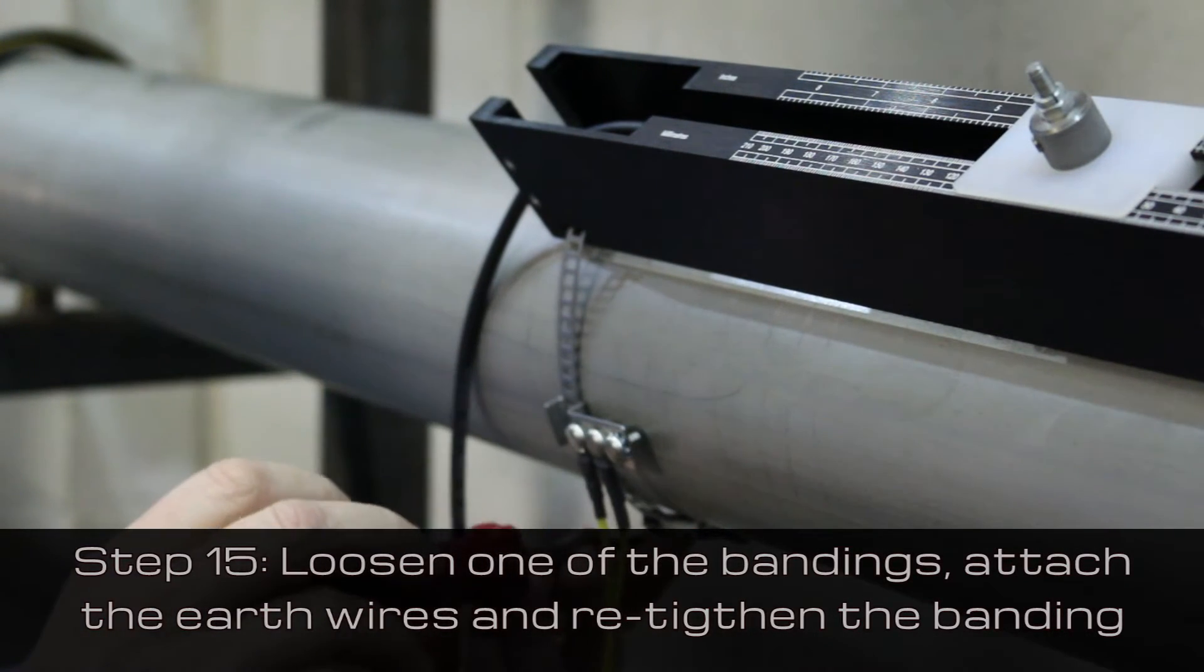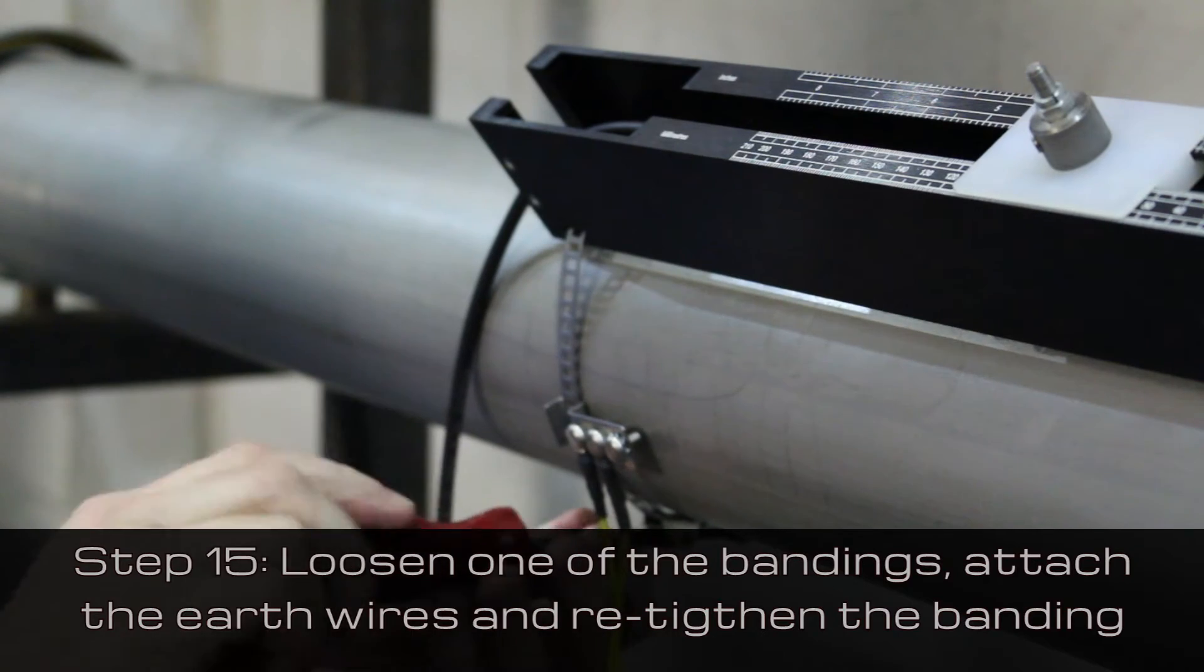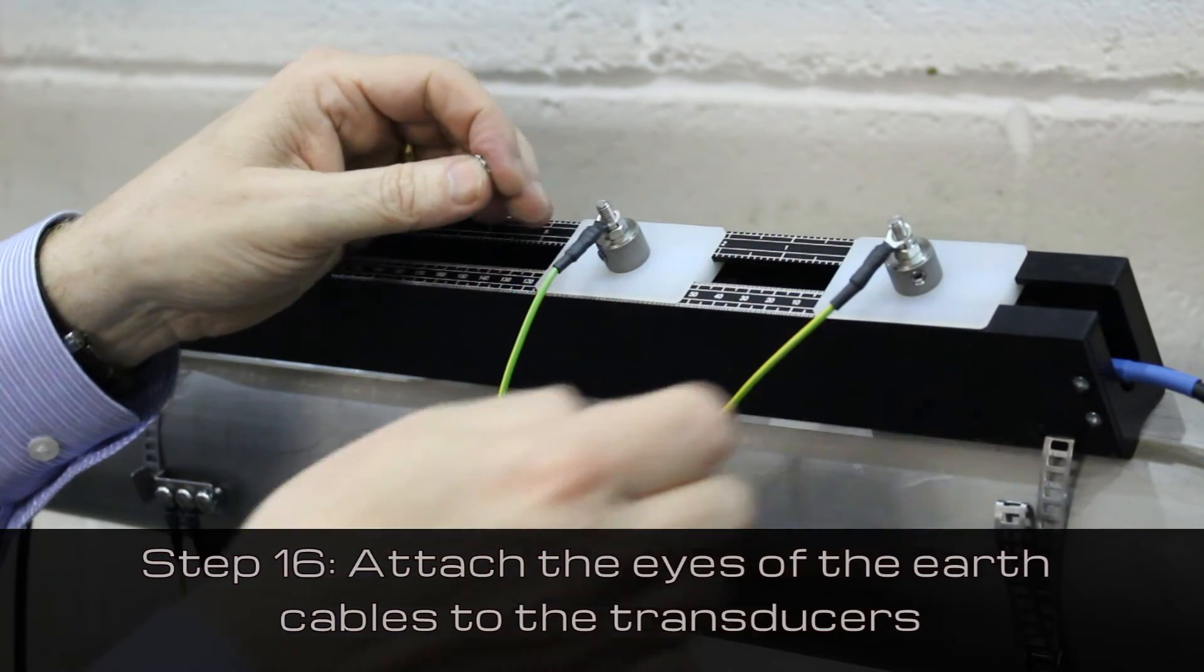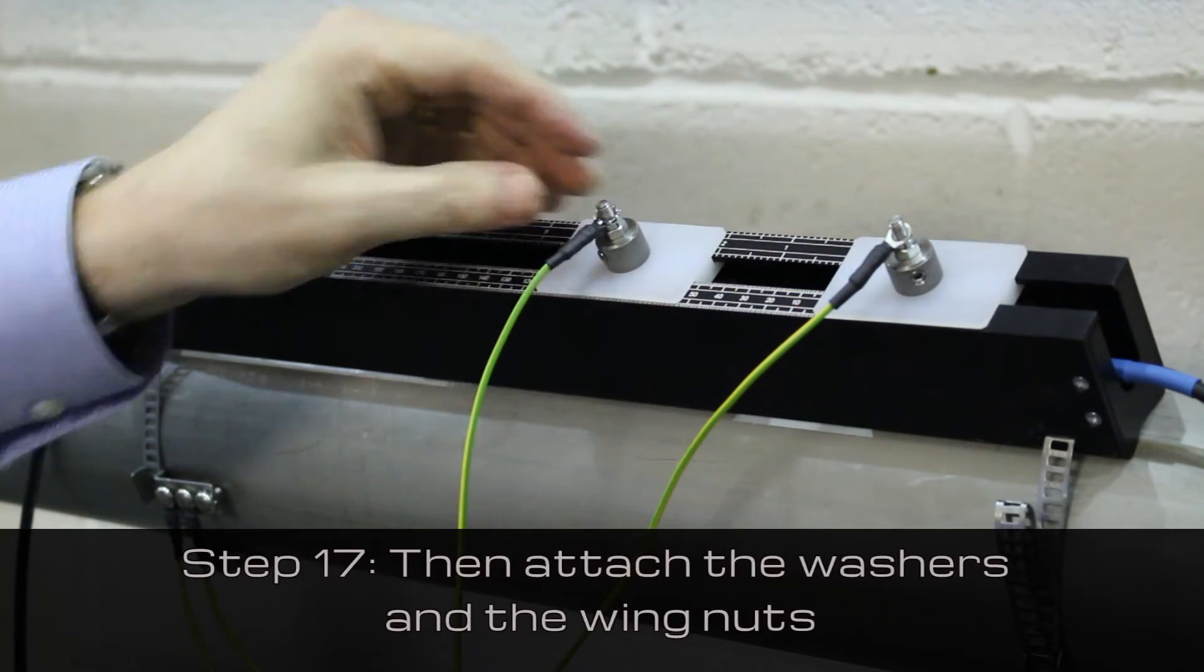Loosen one of the bandings, attach the earth wires, and retighten the banding. Attach the eyes of the earth cables to the transducers followed by the washers and the wing nuts.